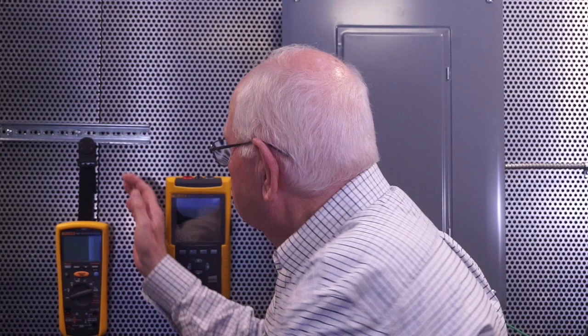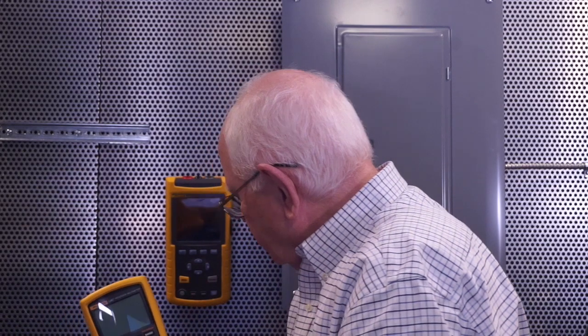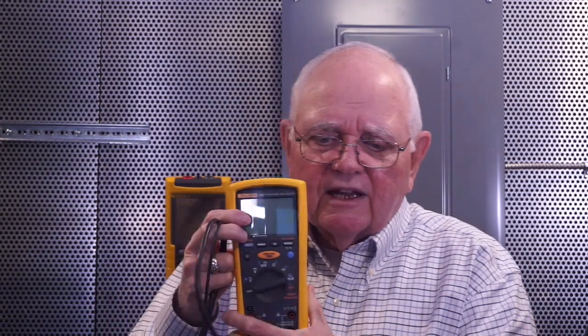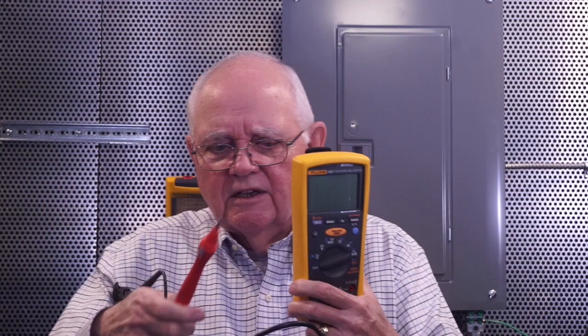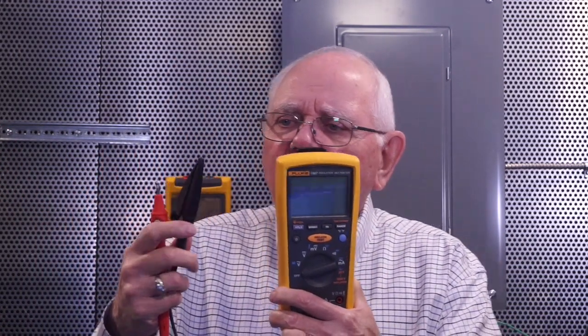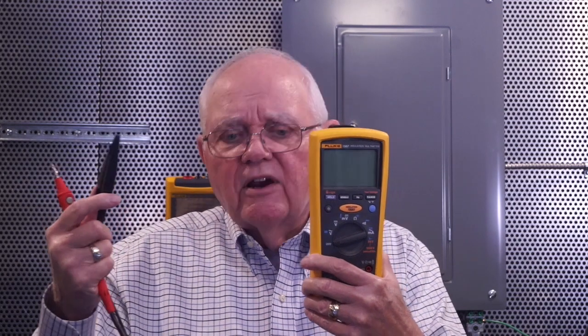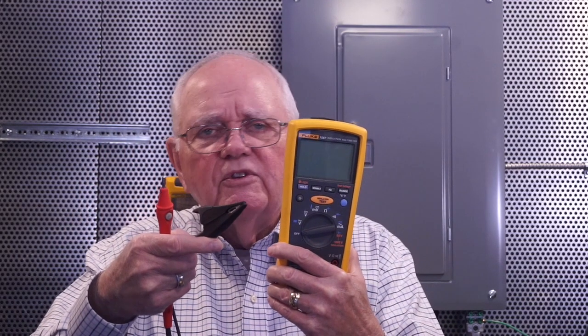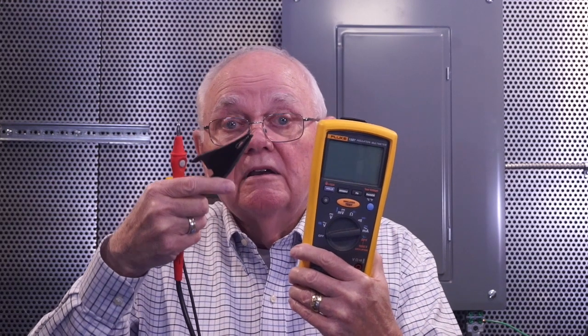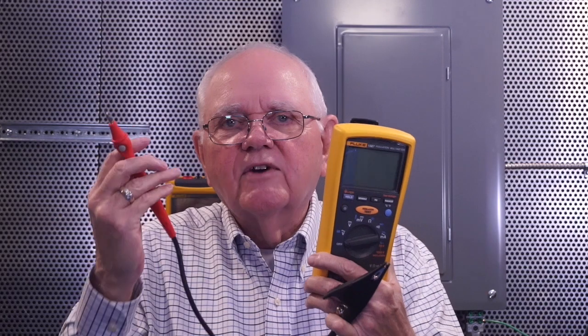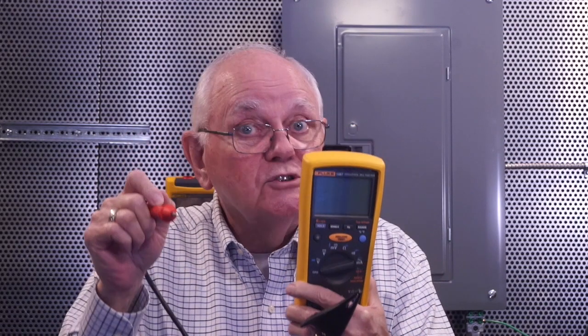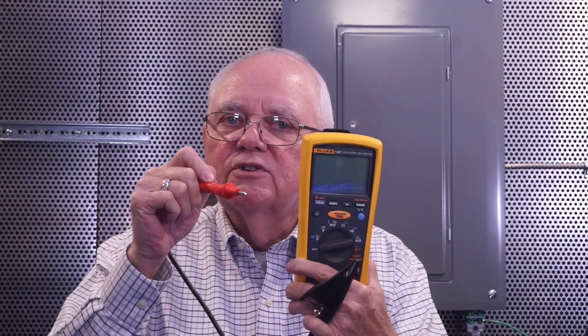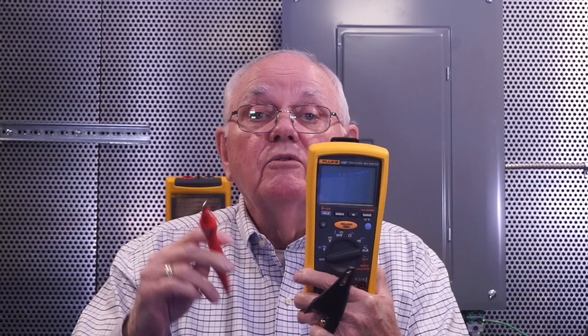Let's take some examples of that. Now, if I'm going to do a standard test on, let's take something like this, an insulation resistance tester. So now I've got an insulation resistance tester and a couple of leads I could plug into it here. And so I have a motor. I've de-energized the motor. I've verified it's an electrically safe work condition. I can clip this black test lead onto the frame of the motor or some good grounding connection on the motor. And now I can take the red test lead and touch it to the de-energized terminals right on the motor, and I can measure the resistance of those windings. And they have to be within a certain value.